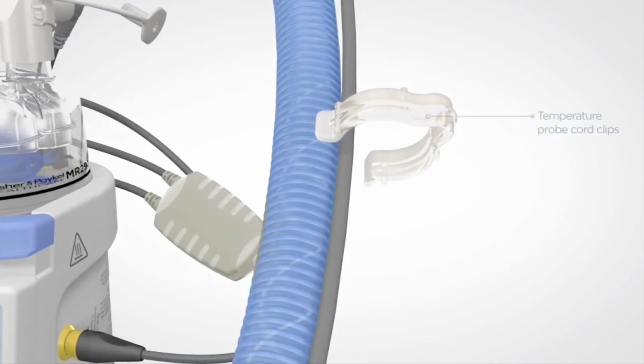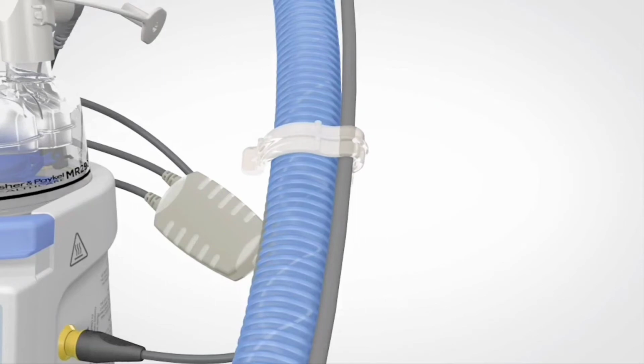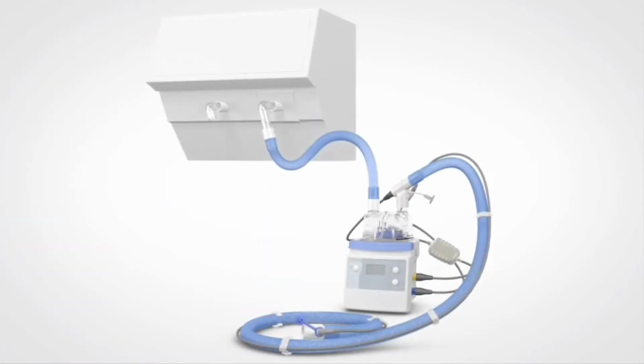If included, attach the temperature probe cord clips to hold the probe wire against the breathing circuit. We have now set up the inspiratory limb. For dual limb applications, such as invasive ventilation and ventilator-driven non-invasive therapy, an expiratory limb is required.